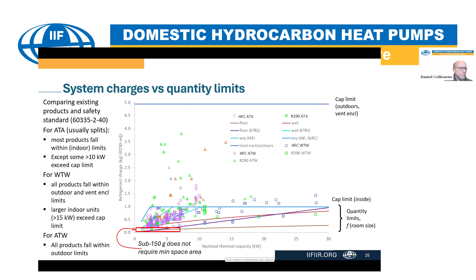is adjusted according to the density of R290. So overall the graph shows that at least for air-to-air systems, the vast majority of systems fall under the charge limits imposed by the standard, and for air-to-water or monoblock systems, water-to-water as well, most of those fall below the 5 kilogram limit as well. So it's just a general overview to illustrate that at least at the moment, the majority of systems can adhere to the requirements within the standards. There are, of course, exceptions to that.